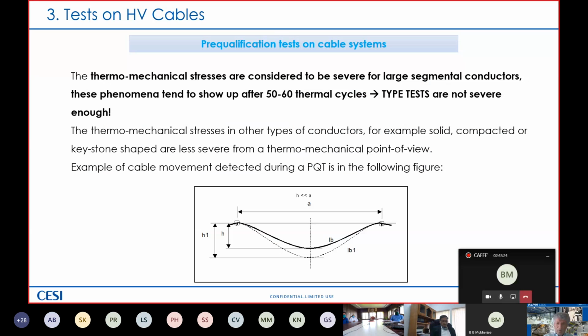As far as loading and unloading is concerned, you can have this kind of so-called brief of the cable, at the end of the cable system, that is the place where you have the cable termination, or even more important, whenever you have joints. These are kilograms that the copper or the aluminum pushes against your accessory. And this, believe me, is one of the most severe causes of failure in accessories along real life, and of course along a pre-qualification test simulation.